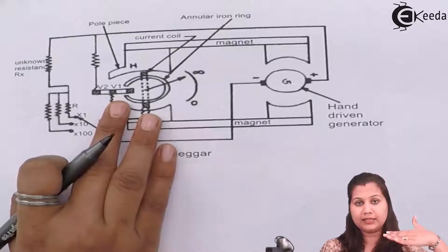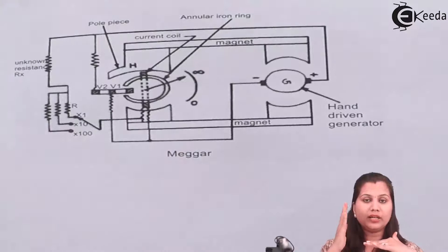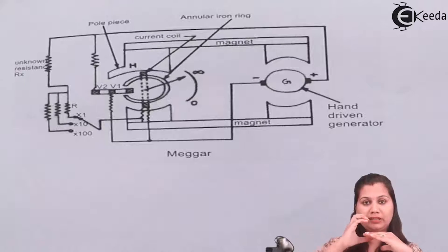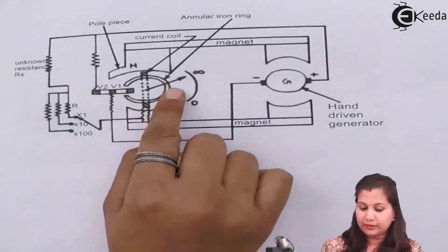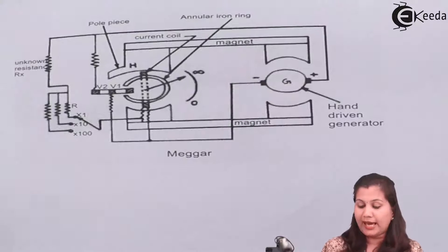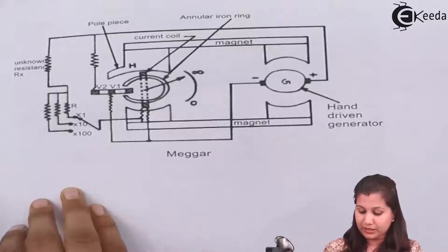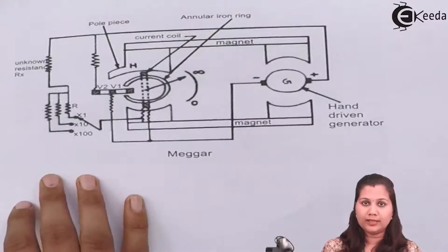The pointer moves over the scale from zero to infinity. When V1 is in the strong magnetic field — in the horizontal position between the C-shaped annular ring — the magnetic field is very strong and the pointer will be at the zero position, as maximum torque is exerted. When V1 is in a weak magnetic field the pointer will be at the infinite position, meaning a very high resistance is present in the circuit which is not allowing current to flow.